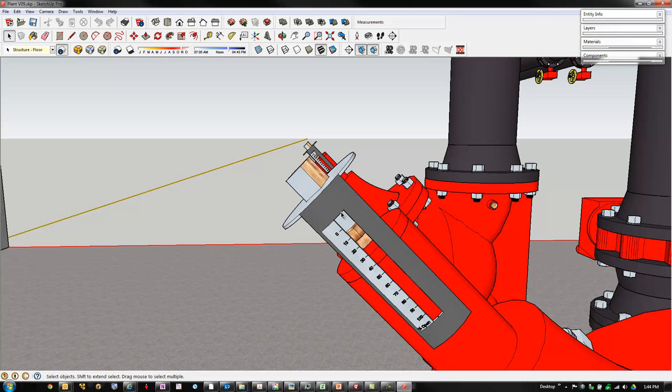But the real clue is the fact that this valve is throttled, which means there's potentially an opportunity to save energy. Because what's going on here is that water is flowing through the pump, flowing through this valve. Because the valve is throttled, there's a pressure drop there, and that pressure drop represents energy.